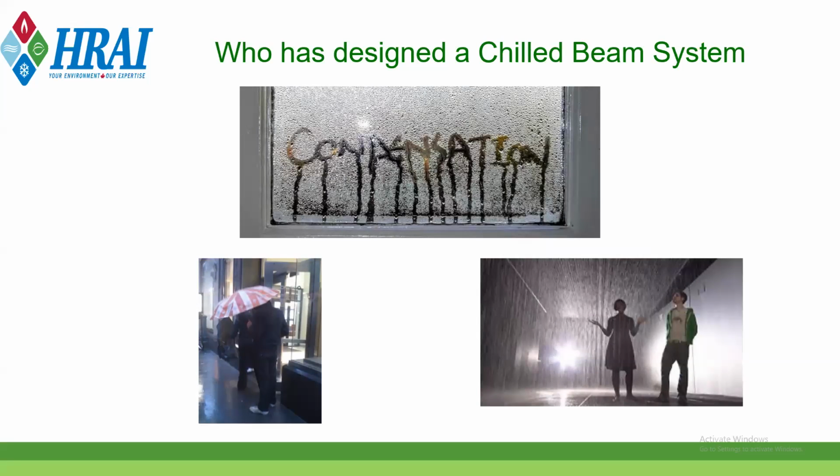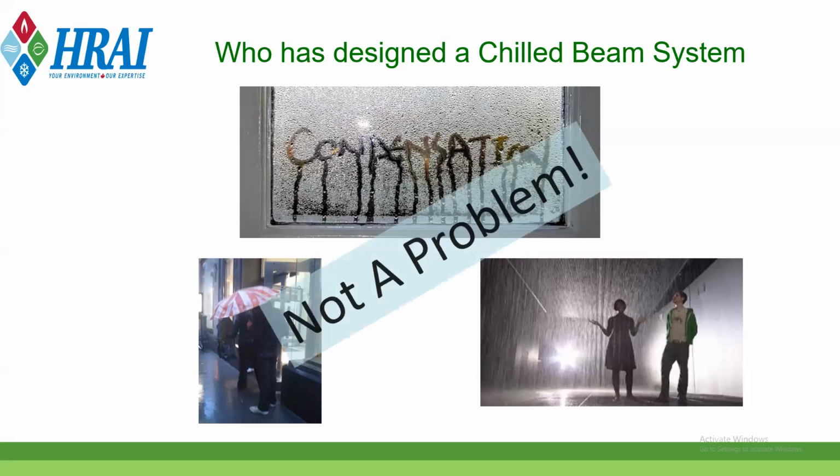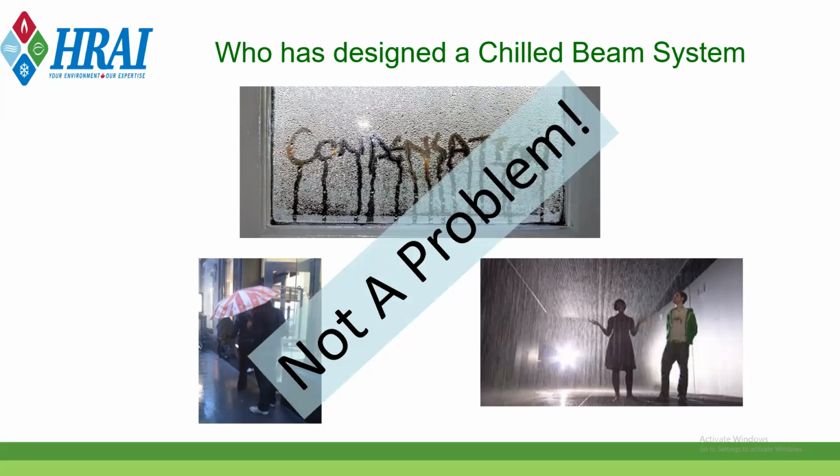When we talk about operating chill beams, again, we're talking about surfaces that are exposed within a warmer space. When you introduce cooled or chilled water to it, condensation could become a challenge. That is one of the primary things that we need to consider when we use an active chilled beam system as an example, and we'll address how we can solve that potential challenge.